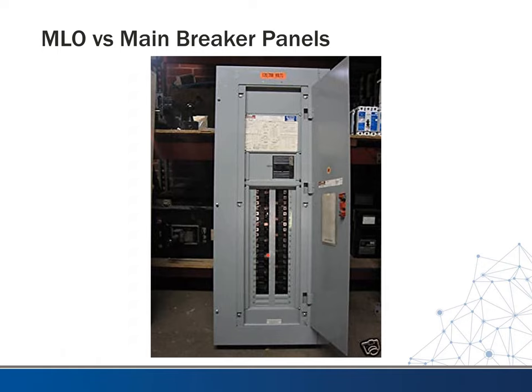So here's one with the cover on. And again, you can usually tell if it's a main breaker panel. It'll have this very large breaker, usually on the top or the bottom where the feeder comes in. So without pulling the panel cover off, I can tell this is more than likely a main breaker panel, and then that feeds the bus here that's using the branch circuit breakers coming off there.